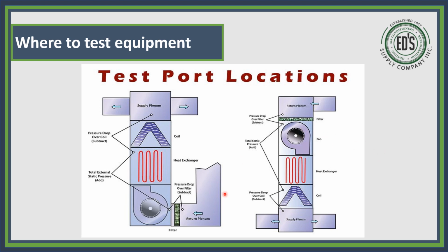So now we want to look at this gas furnace. You have your blower motor here, you have your heat exchanger here, and you have your separate coil on top of that. And then we have this return plenum. Now, I call this a deadhead system. This is probably one of the most common things because when you're using a furnace, you have to allow for the coil on top of that. And this is one of the most common installs. You always see a filter right here on the side of these furnaces. And you have plenty of ductwork, it looks like here. So we're going to see there are a few issues with this install.